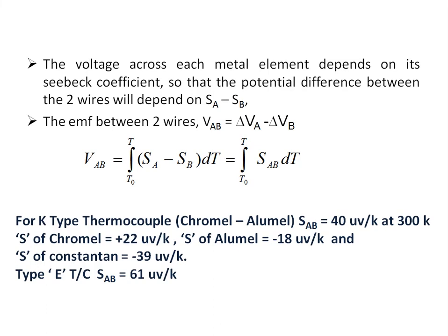For a Type K thermocouple, which is made up of chromel and alumel, chromel is the positive end and alumel is the negative end. The Seebeck coefficient S_AB is 40 microvolts per Kelvin at 27°C. The Seebeck coefficient of chromel is +22 microvolts per Kelvin and that of alumel is −18 microvolts per Kelvin. The Seebeck coefficient of constantan is −39 microvolts per Kelvin, so the Type E thermocouple made of chromel and constantan has a Seebeck coefficient of 61 microvolts per Kelvin (22 − (−39) = 61 µV/K).